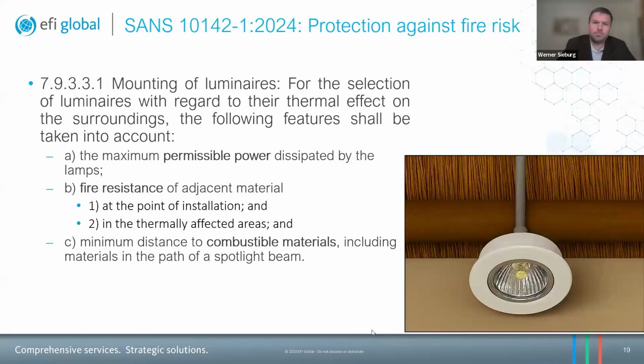Thanks, Kashan. Next slide. Right, now let's move to specifically the mounting of luminaires. And I think in this illustration, you can also just see the specific filament lamp that I'm speaking of. It was very much in fashion, let's say, 15, 20 years ago, not as much now with the rise of LED lamps. The selection of luminaires with regards to the thermal effect on their surroundings, right? So we can all agree that these lamps do get kind of hot, and that the fittings and the holders of these lamps need to be specifically designed for that purpose.